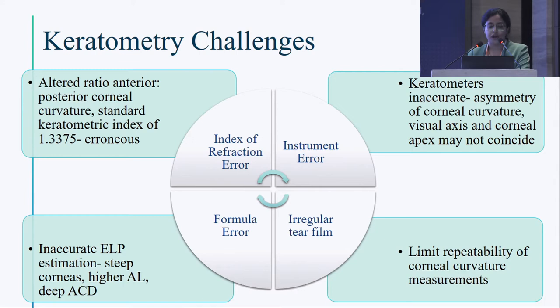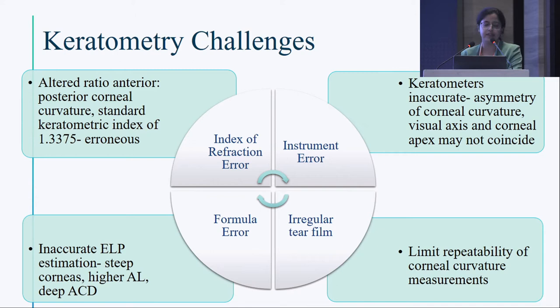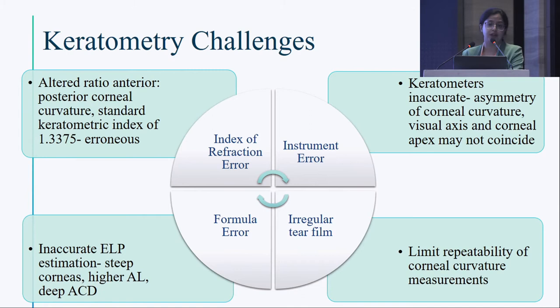Keratometry challenges include index of refraction error, instrument error, formula error, and irregularity of tear film. Conventional keratometers assume a fixed anterior-to-posterior corneal curvature ratio using the standard keratometric index of 1.3375, which does not hold true in keratoconus. The anterior-to-posterior corneal curvature ratio is altered. Keratometers are also inaccurate because asymmetry of corneal curvature is not accounted for, and visual axis and corneal apex may not coincide. Formula errors arise because newer regression formulas are based on effective lens position estimation, which is inaccurate due to deeper anterior chamber depth, higher axial length, and steep corneas. Irregular tear film also limits repeatability of corneal curvature measurements.